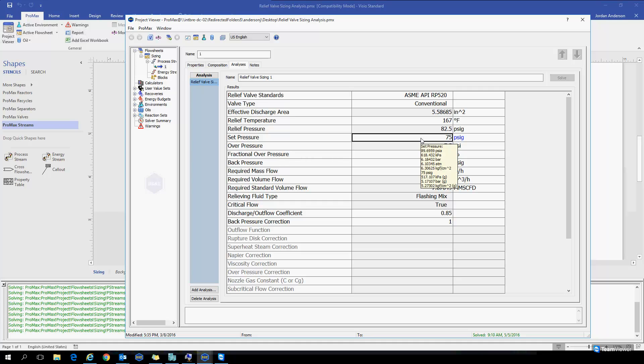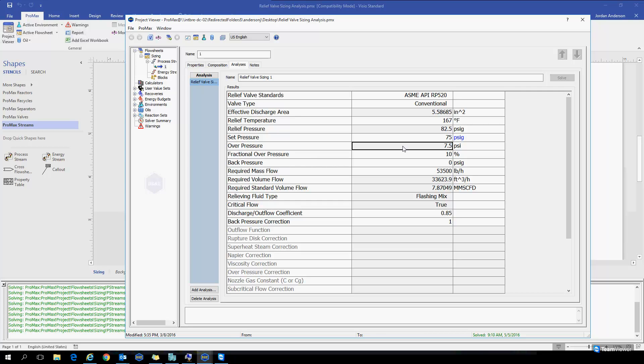The set pressure is your normal, standard pressure that you expect to be operating at. The relief pressure can be calculated in three different ways. We could, as a user, manually input a relief pressure, or we could manually input the overpressure, which is how much more pressure we expect to be above the set pressure. Or the most common way of setting this relief pressure is by setting a fractional overpressure, which by default here is saying that our relief pressure will be 10% more than the set pressure. But this value could be changed according to the situation you're sizing for.